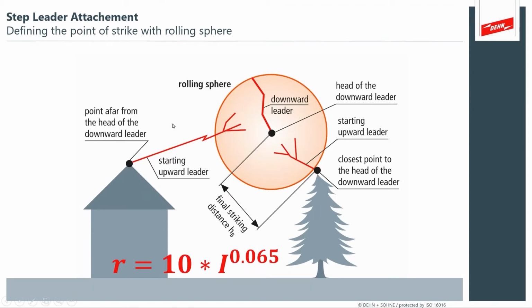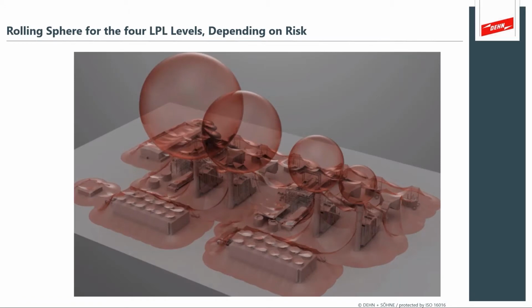What we know about the propagation of lightning is it's the movement of charge in the atmosphere, and it provokes an electric field, and that electric field pulls step leaders. It essentially provokes step leaders to jump, especially at that final striking distance. And what we understand about lightning propagation is that the radius of that potential strike is a function of the current, that lightning strike energy that we just looked at. So if you're closer to the charge, you'll provoke a shorter spike, and a lower lightning strike energy will lead to a smaller step leader. And that's reflected in the rolling sphere.